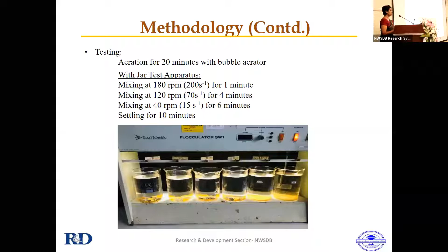These are the results we obtained. When alum was used for the raw water, we didn't see thick flocs formed, and the flocs formed were small. Therefore, the maximum efficiency we could reach was below 60%. And then we used the polyaluminium chloride. With polyaluminium chloride, when the pH is from 7.5 to 8, we could reach an iron removal of more than 96%, and the residual iron concentration was in the range of 0.1 milligrams per liter, which is satisfactory.